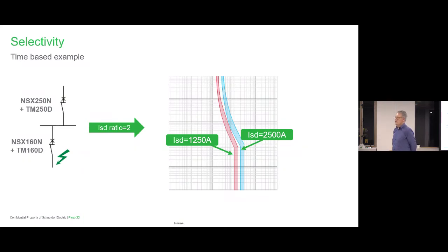Because if that's a large backbone and it's static, that'll never change often. So all we say as a supplier is that if you have a chance to keep the same brand all the way through, please do so. If you don't, for some reason, then you have to take into consideration under short circuit faults that you really don't have a full guarantee. But if you had a 250 amp upstream and a 100 amp downstream, which is 2.5 times, you would expect every day of the week that there'll be no problem with that.